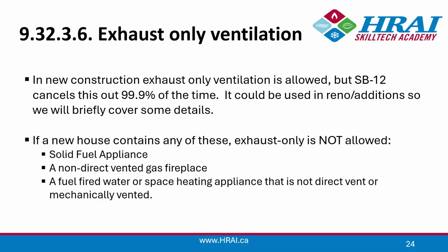A non-direct vented gas fireplace, also a problem. A fuel-fired water or space heating appliance that is not direct vent or mechanically vented. So anything B-vent, if there's still stuff out there, and I know there are. However, when we get into these in renovations and so on, oftentimes they're replaced with direct vent appliances. So if any of these are involved, then of course exhaust only is not allowed.